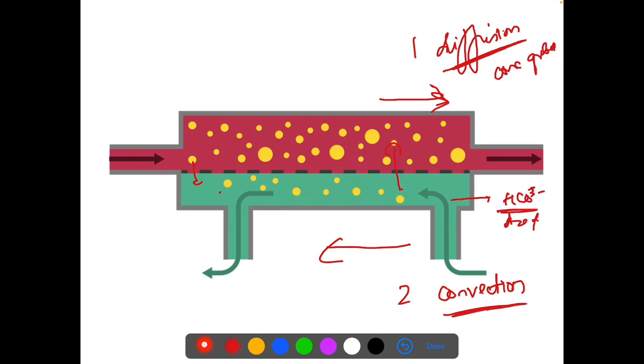The other method is convection. Generally the large molecules are removed from the blood into the dialysate by convection. This takes place because of the hydraulic pressure gradient. The solvent or fluid that moves from the blood compartment to the dialysate carries some solute along with it because of the pressure gradient — that is called solute drag. As the solute size increases, the rate of diffusion decreases in a logarithmic scale.